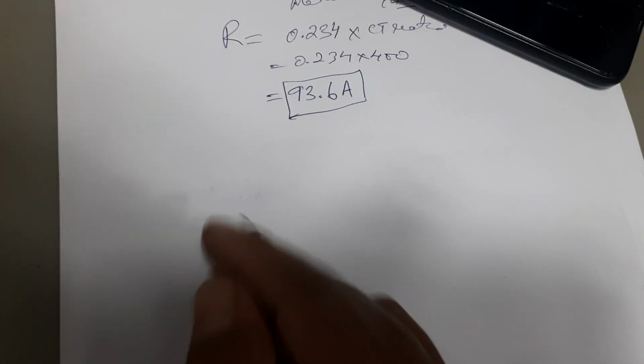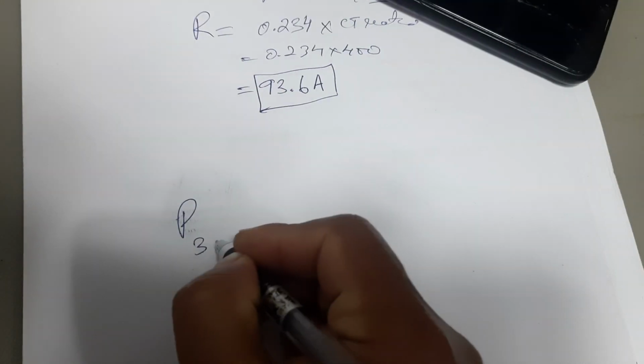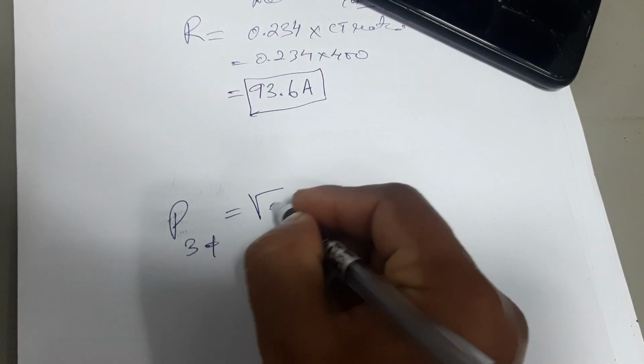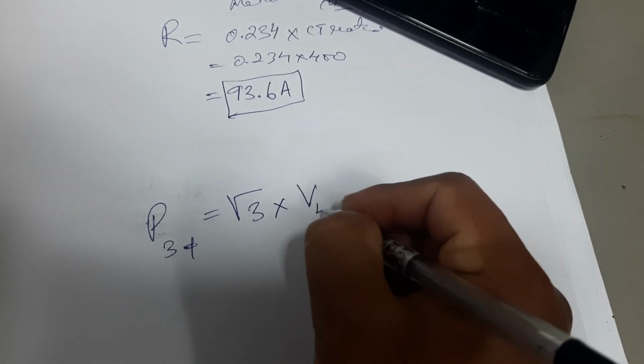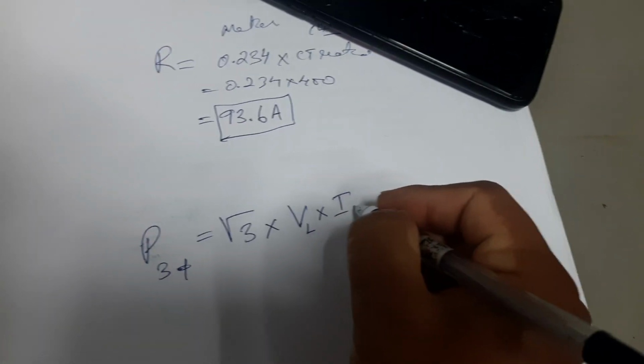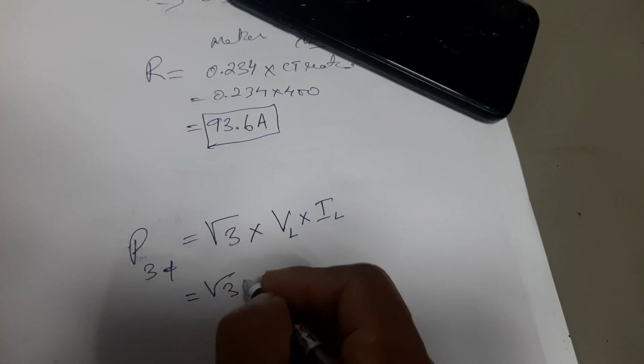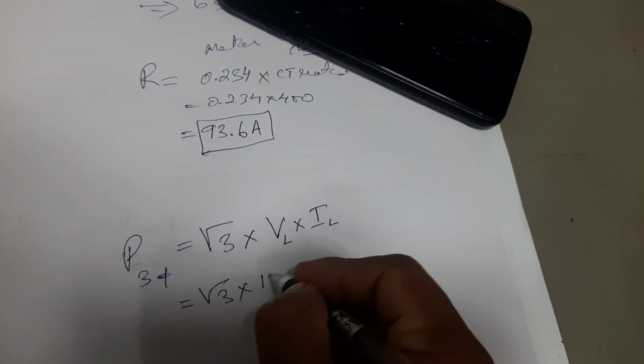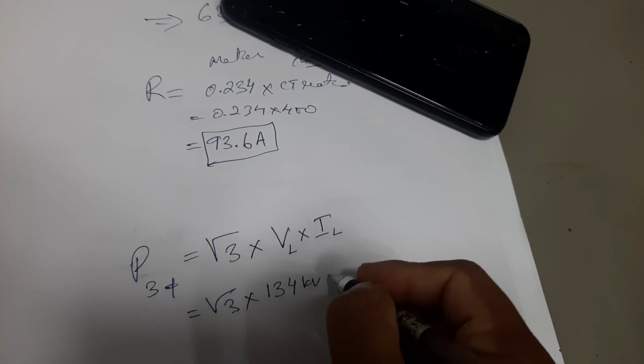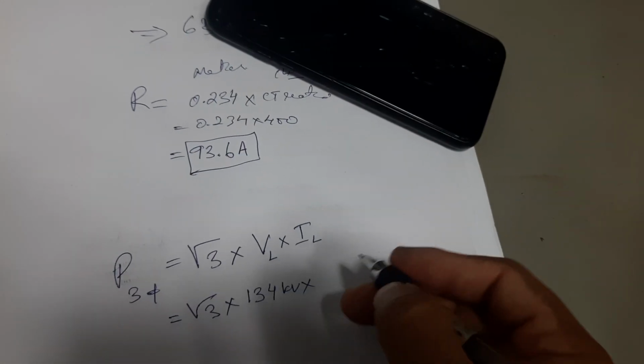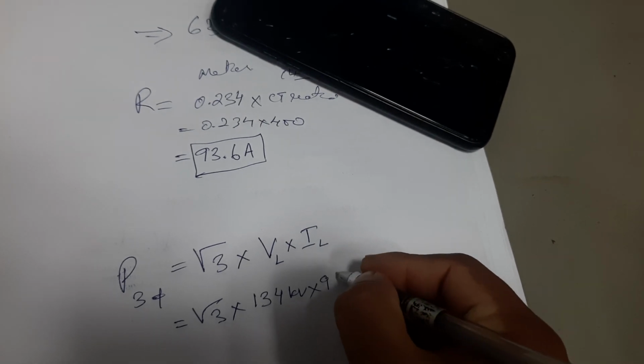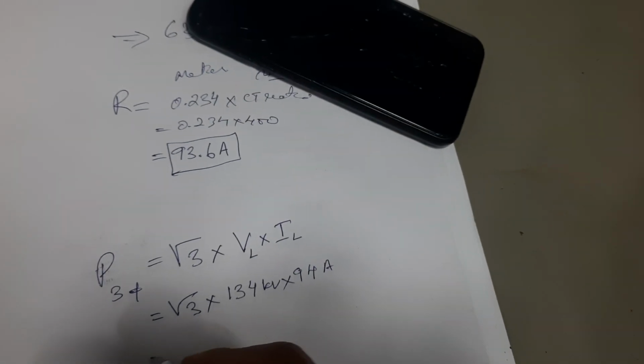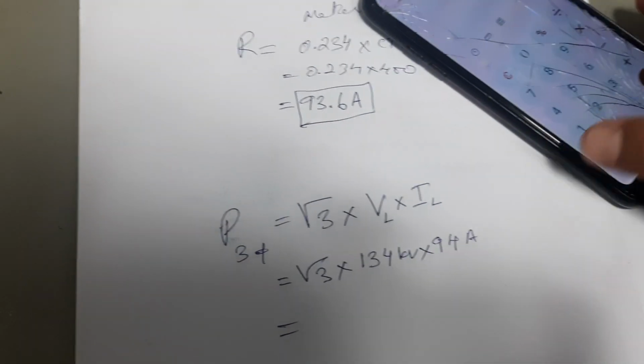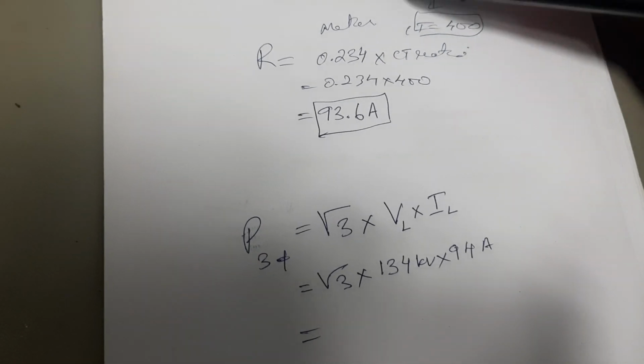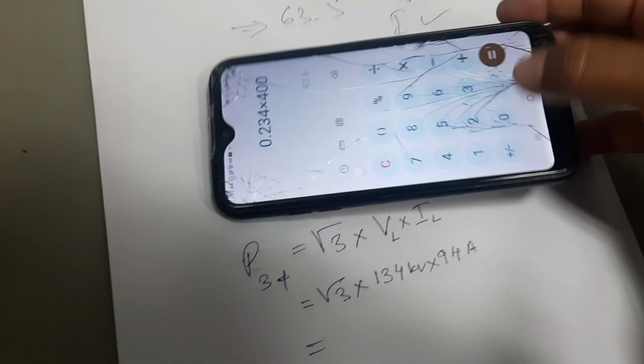Okay, we'll just calculate the power. The three-phase power will be, the formula is root 3 into our line voltage or bus voltage into line current. So I'll put here root 3 into line voltage is 134 kV. Only the unit, no need to write, it's only something that we have to understand. And I'm taking line current from the BCU, which is 94 ampere. So if I calculate this, how much am I getting? This is just to verify whether your BCU or your SCADA is reading the correct value or not.